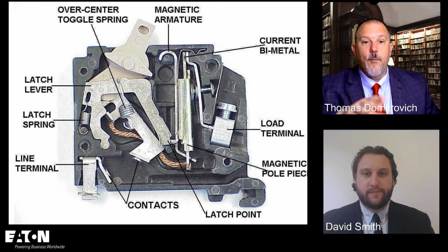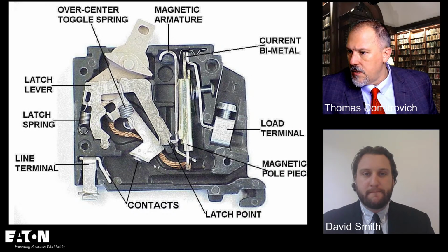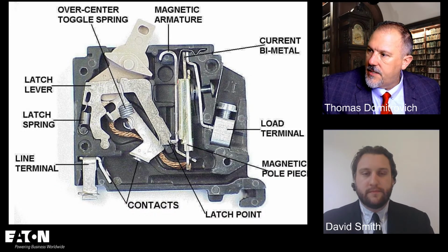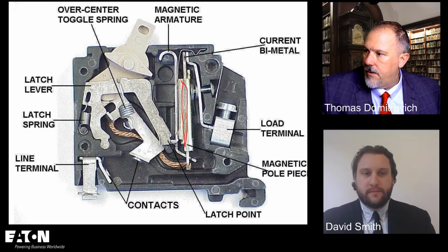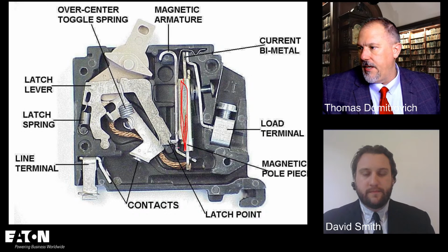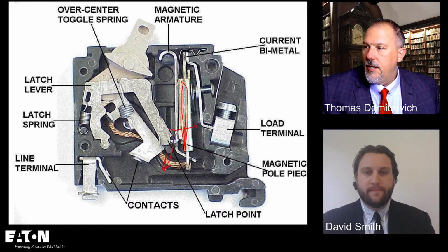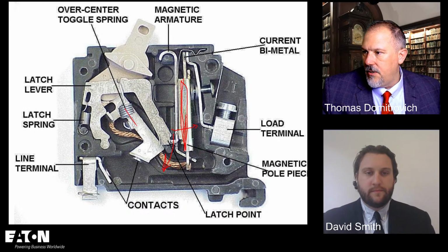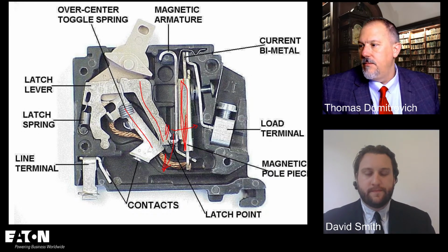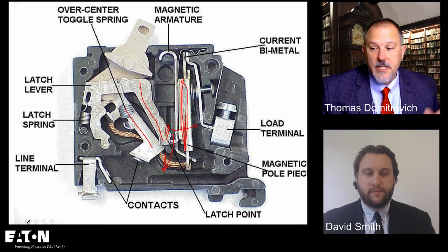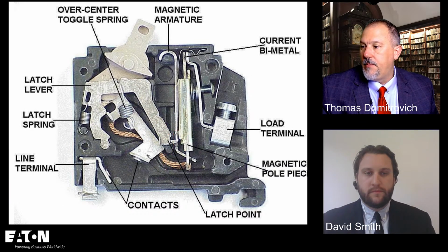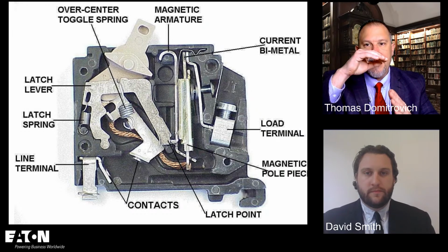Right. And what happens is, to your point, it drops. So this is your bimetal right here. Then it will bend, and then my latch will fall. Right. Okay. This here is your arm. This is your latch. This is a breaker in the open position, so it's got to move up. But in any case, you said it exactly right. That metal will bend, the latch will fall, and it will open.